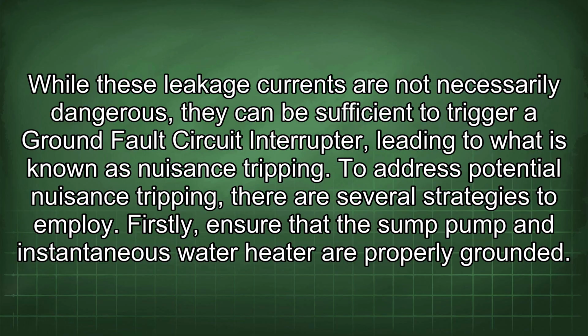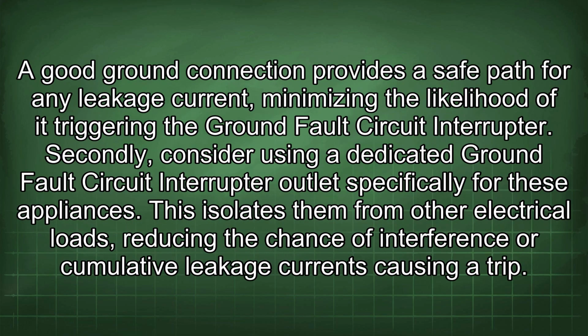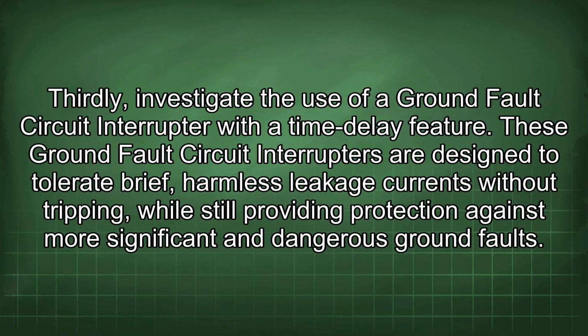To address potential nuisance tripping, there are several strategies to employ. Firstly, ensure that the sump pump and instantaneous water heater are properly grounded. A good ground connection provides a safe path for any leakage current, minimizing the likelihood of it triggering the ground fault circuit interrupter. Secondly, consider using a dedicated ground fault circuit interrupter outlet specifically for these appliances. This isolates them from other electrical loads, reducing the chance of interference or cumulative leakage currents causing a trip. Thirdly, investigate the use of a ground fault circuit interrupter with a time delay feature. These ground fault circuit interrupters are designed to tolerate brief, harmless leakage currents without tripping, while still providing protection against more significant and dangerous ground faults.